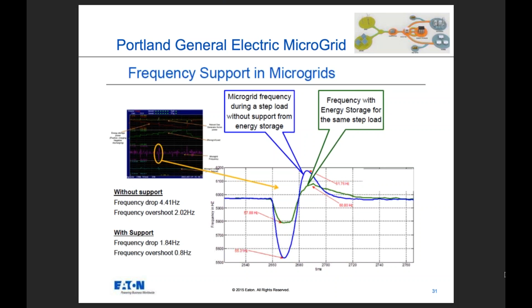But this shows the difference of having these very fast inverters responding very quickly to limit it. So you see, we would have went down to 55 hertz, but we're only going down to 58 hertz. It doesn't sound like a whole lot to you, but actually it's a lot when it comes to the electrical side. Next slide.